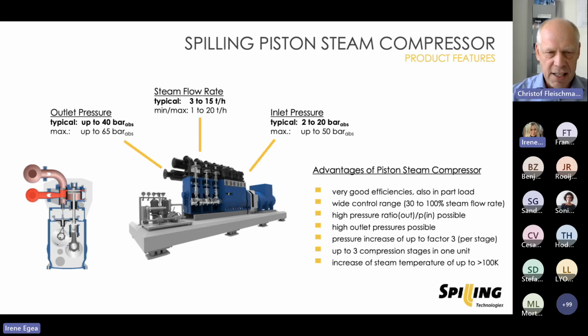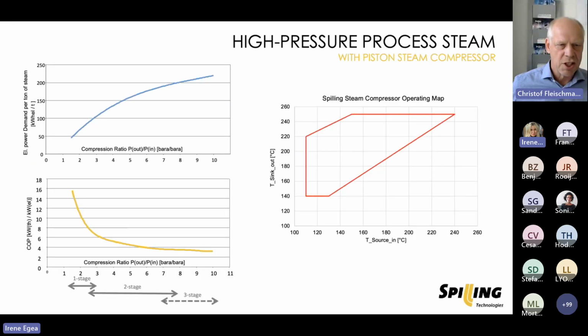On the next slide, again, these efficiencies are shown. On the left, below, the yellow curve shows the COP as a function of the compression ratio. For example, when we compress steam with a factor of 3, from 4 bar to 12 bar, so when we triple the pressure, we get a COP of about 6, meaning that the thermal output coming out of the compressor is 6 times as high as the electrical power consumption of this unit.